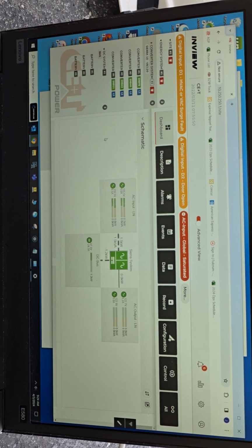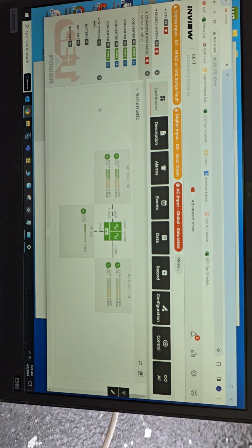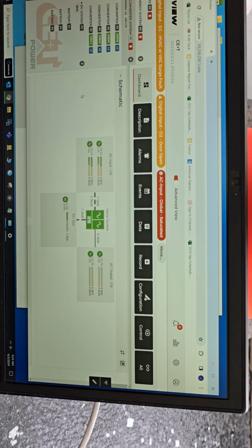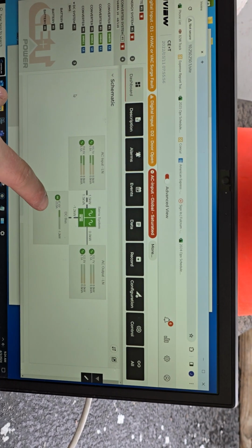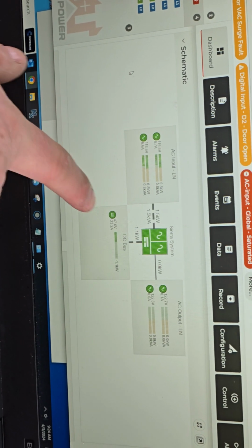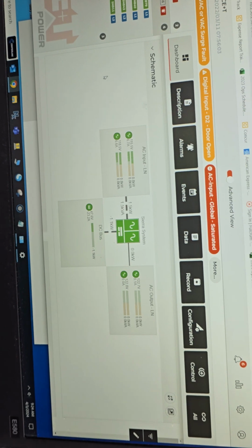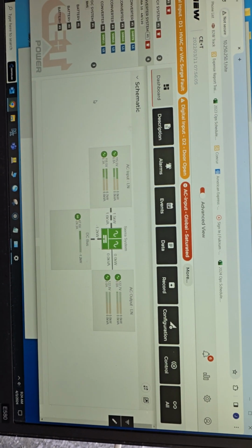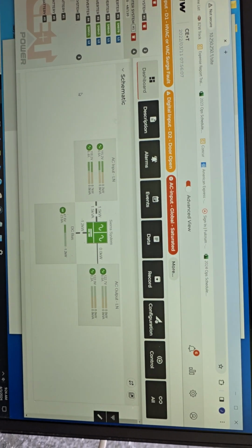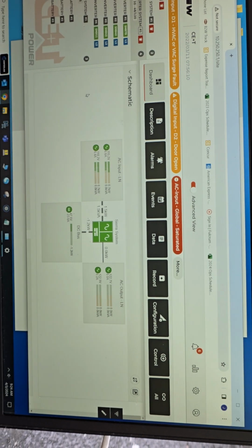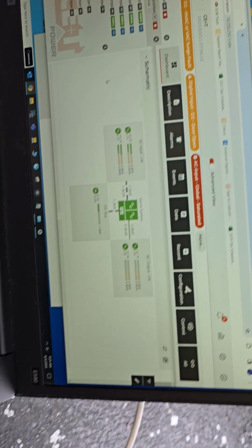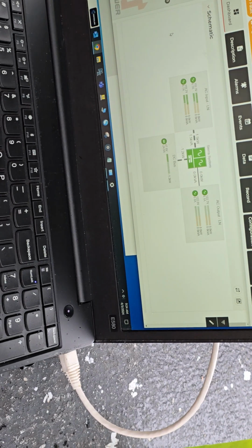Right. Well, so these are the numbers that you should be seeing. And so this neg 24 amps, that's the battery charge. So that was 40, which was like kind of overriding the system a little bit, so we had to lower that to 24. Okay. And the only alarms that we should see when we're done are You can turn on AC output.